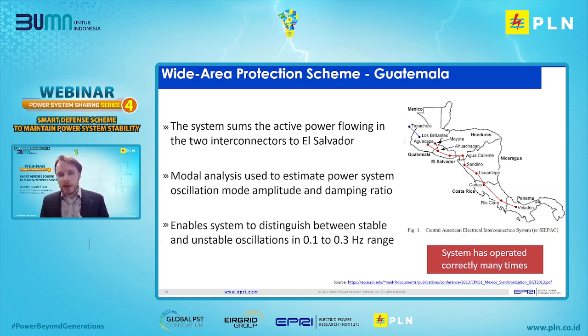So if there are oscillations, but they are heavily damped, the system takes no action. But if there are major oscillations with large swings and they are not damped, then the system takes actions to mitigate those. It particularly looks for unstable oscillations in the 0.1 to 0.3 hertz range. The system has operated successfully many times in the last 8 years, and they've had a very positive experience. This is as a result of spending a lot of time doing quality testing and evaluation and maintenance of the scheme to ensure that it works well. So we think this is an example of schemes that will be used quite a lot going into the future, where they're using advanced technologies and leveraging PMUs and synchrophasor schemes to deploy such an advanced scheme.